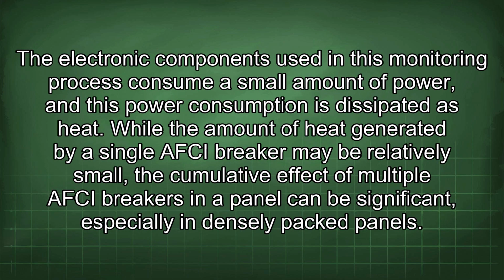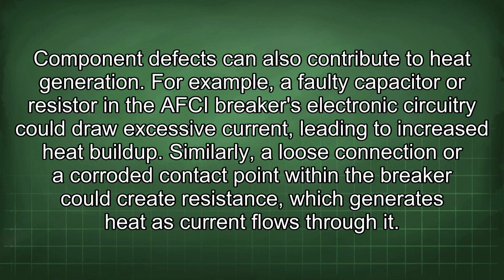The electronic components used in this monitoring process consume a small amount of power, and this power consumption is dissipated as heat. While the amount of heat generated by a single AFCI breaker may be relatively small, the cumulative effect of multiple AFCI breakers in a panel can be significant, especially in densely packed panels. Component defects can also contribute to heat generation. For example, a faulty capacitor or resistor in the AFCI breaker's electronic circuitry could draw excessive current, leading to increased heat buildup. Similarly, a loose connection or corroded contact point within the breaker could create resistance, which generates heat as current flows through it.